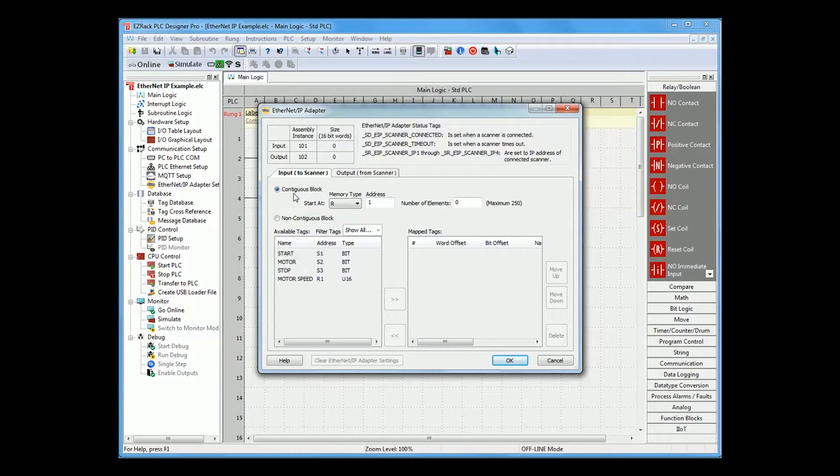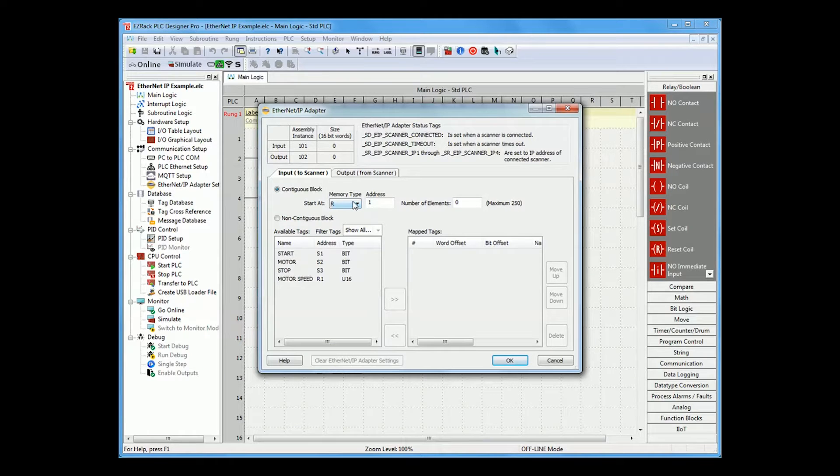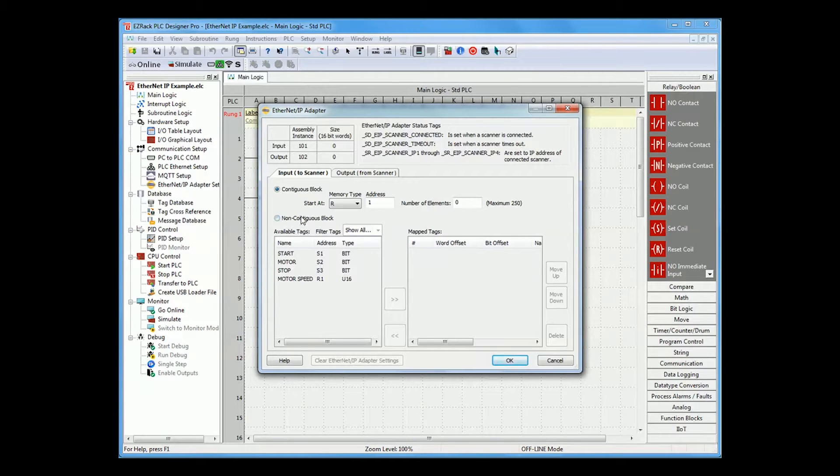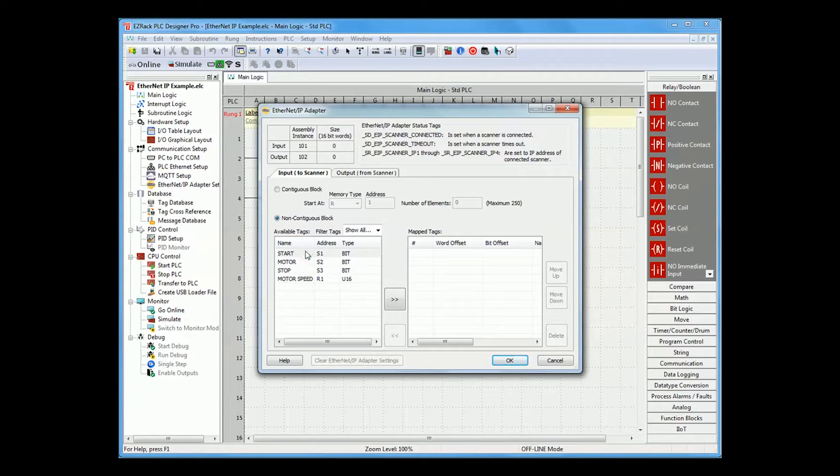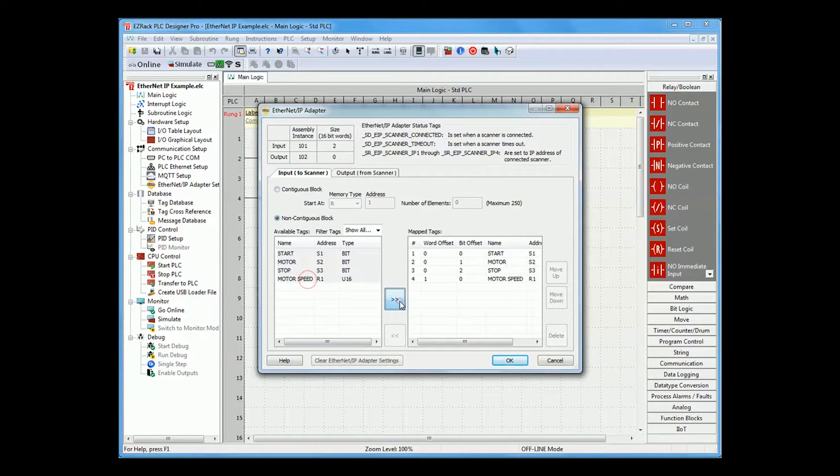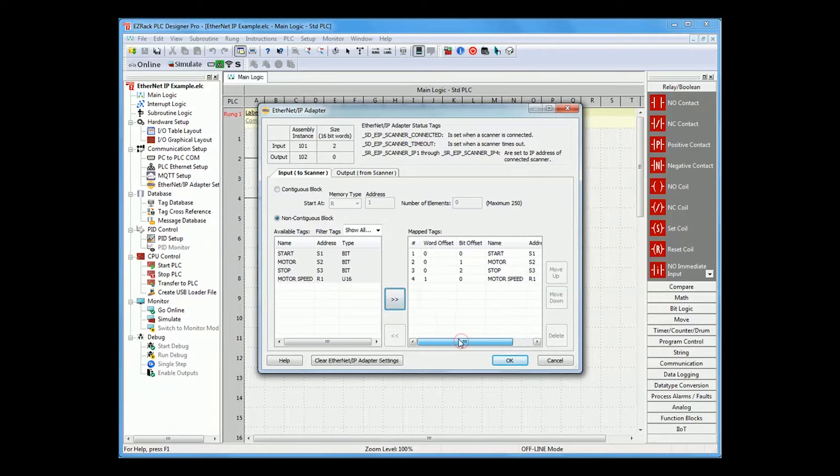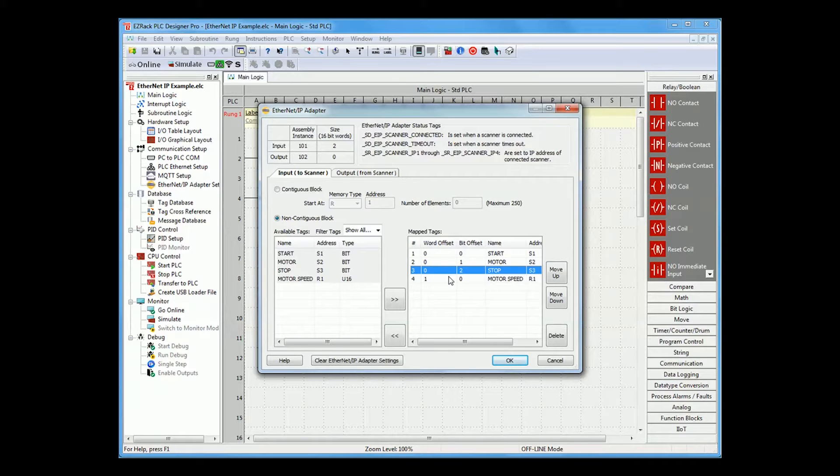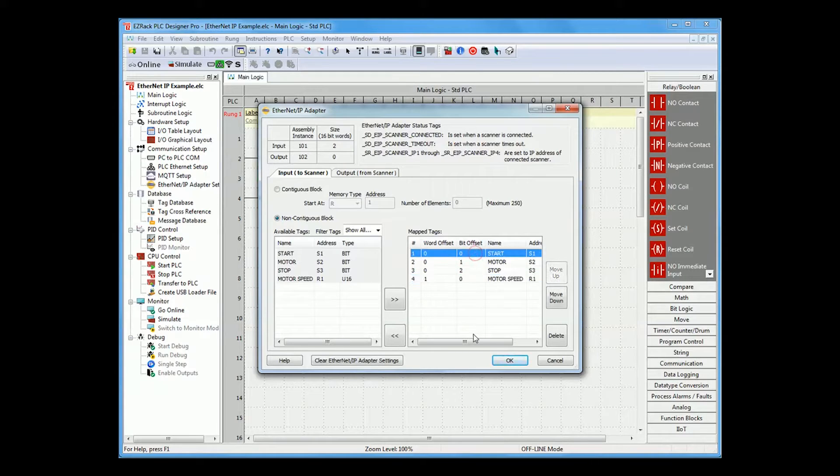You can either send a contiguous block up to 250 elements or you can send a non-contiguous block of registers which you just decide. So for my example, I will use my start, motor, stop, and motor speed. Here you will see which word in the Ethernet IP scanner you're using and which bit for each of these.